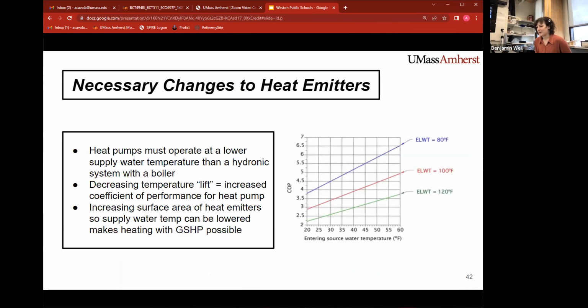Heat pumps need to operate at a lower supply water temperature than a hydronic system with a boiler. Decreasing the temperature lift that the heat pump has to do increases the coefficient of performance for the heat pump, as illustrated by the graph on this slide. Increasing the surface area of heat emitters so supply water temperature can be lowered will make heating with the ground source heat pump possible.